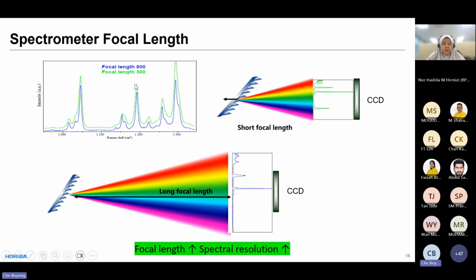Here is the result comparing the measurement of the same sample using two different spectrometers. One has an 800 focal length, one has a 300 focal length. You can see the blue one has more peaks. For example, this part here, you can see this shoulder using the longer focal length spectrometer, but you won't see this using the shorter one. Here is also the same thing. You can see this shoulder in the blue result, but cannot see it in the green result. So a longer focal length will give you a better resolution.